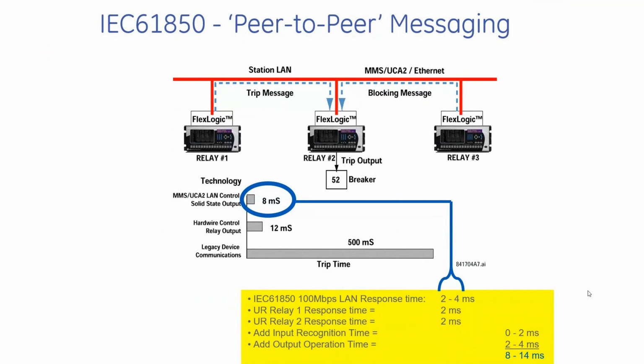One of the applications of using 61850 is via GOOSE messaging. This is to transfer fast peer-to-peer messaging between relay to relay. So we're talking about 2 to 4 milliseconds response time from relay 1 to relay 2, and then once you add the trip contacts and all the input recognition, all that stuff, we're talking about less than a cycle response time from when I initiate at relay 1 to when I get a response from relay 2 to trip the breaker. So very fast communication, a means of doing it over Ethernet communication.